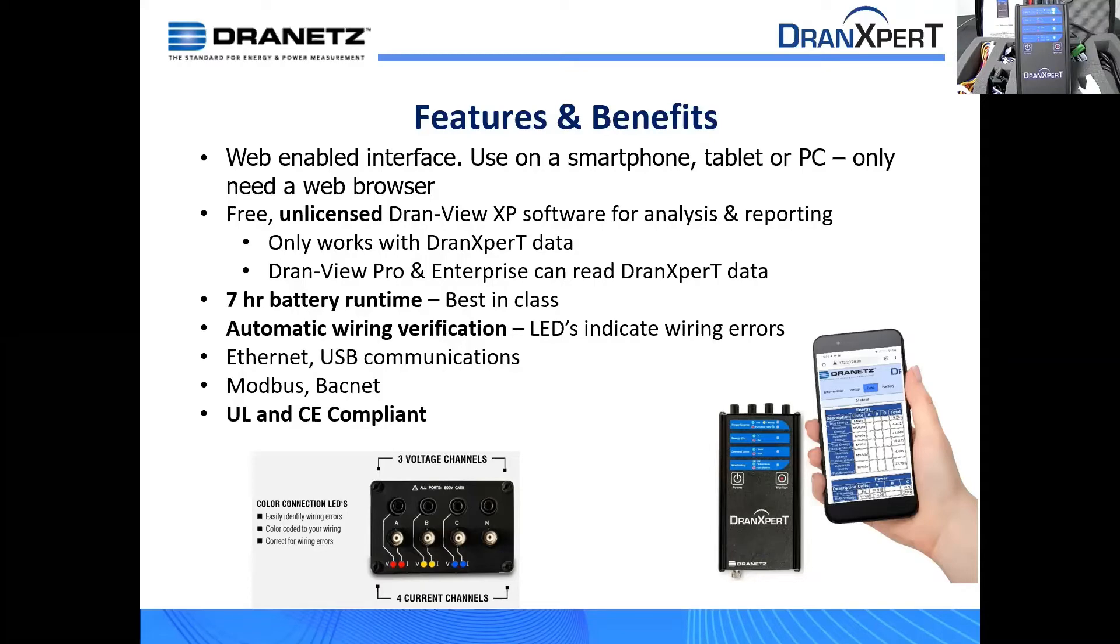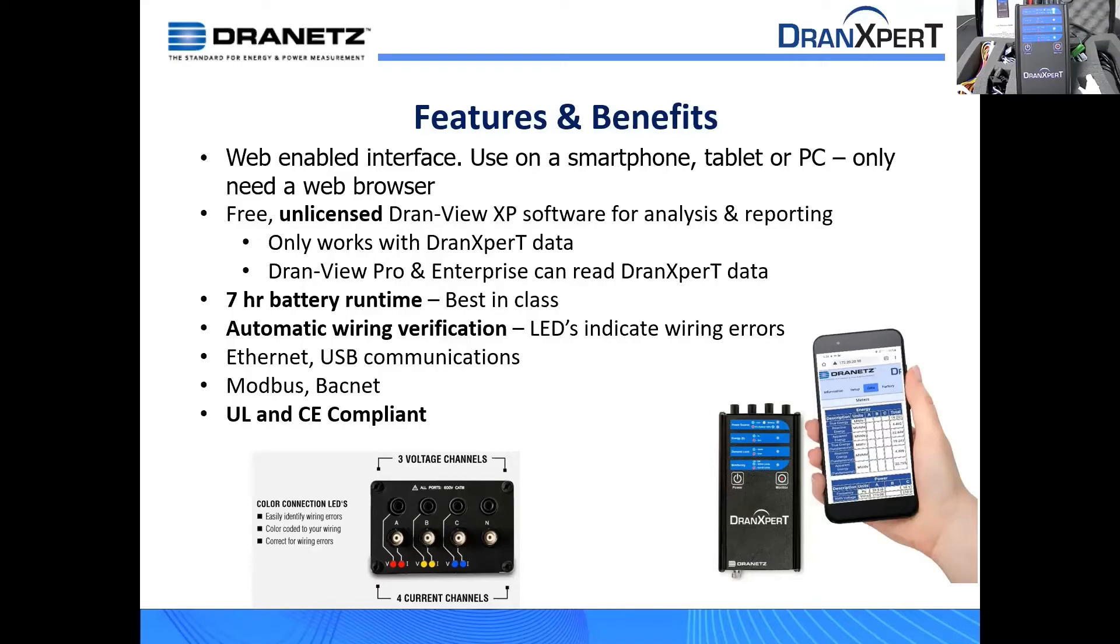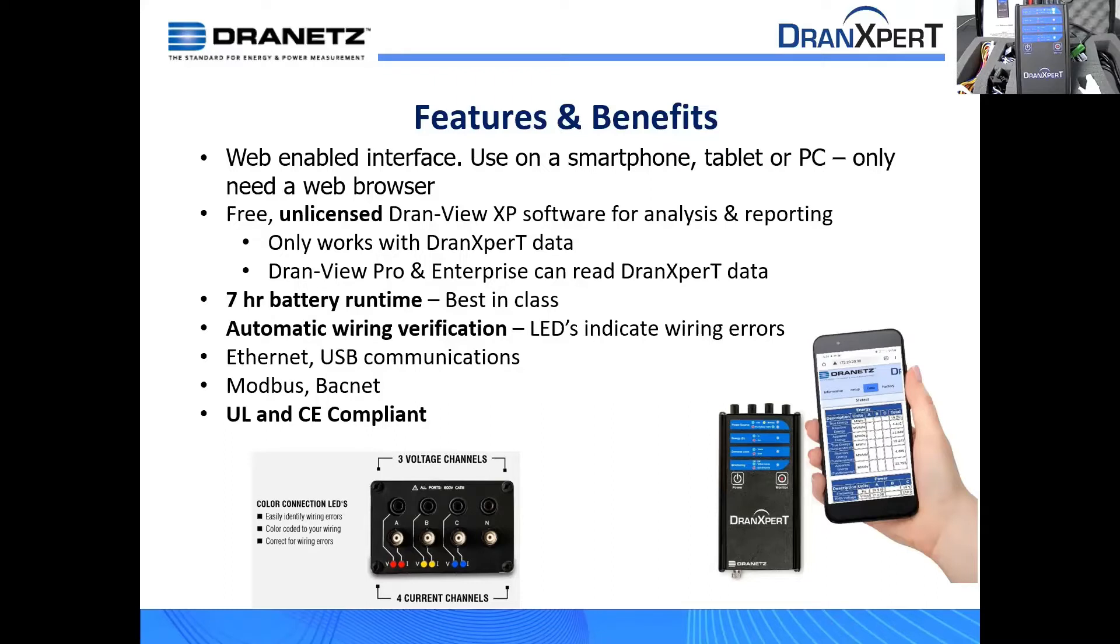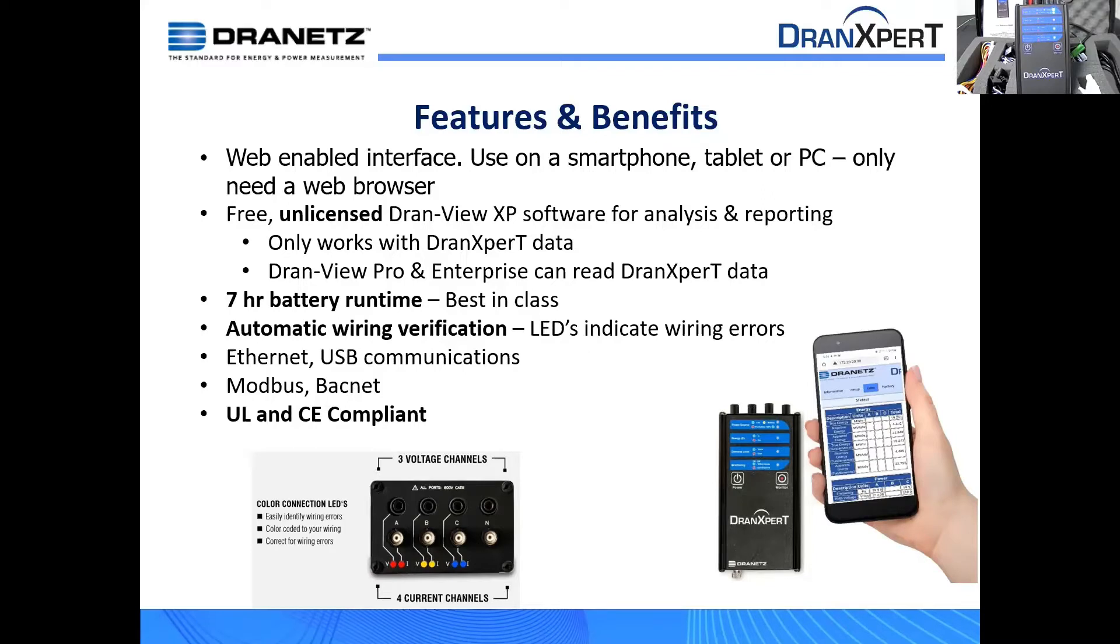So if you're a current Dranview user, just do an auto update on Dranview or go to our website and download the latest version, and then it'll become DranXperT compliant. Just a couple of quick things. DranXperT does have a seven-hour battery runtime, automatic wiring configuration detection. So it'll tell you if it thinks that you are miswired. It is Ethernet and USB capable. It does have Modbus capabilities and BACnet capabilities, as well as it's UL and CE compliant.